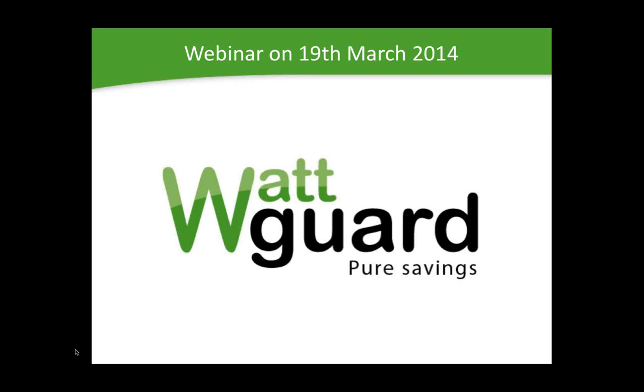So in the new version of the cabinet, there's a software unit embedded in the Wattguard that adjusts to the fluctuation of the voltage, meaning that we have actually optimized the saving possibility by being able to follow the fluctuation in voltage during the day or whatever period you look at. Even also being able to start the light units at a higher voltage and subsequently taking it down to a lower level, which for some types of light units is a great benefit in terms of the wear out, but also in terms of the operation within the factory and so forth. So that is an embedded feature in the new version of the cabinet, and it will be handled by the system automatically.